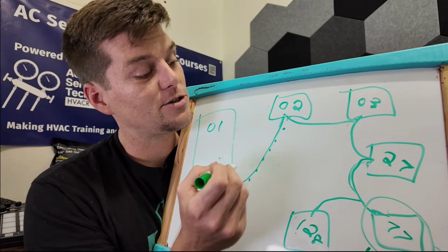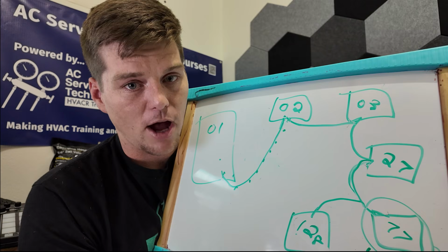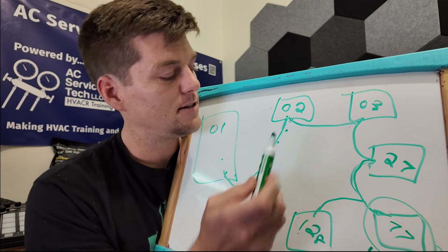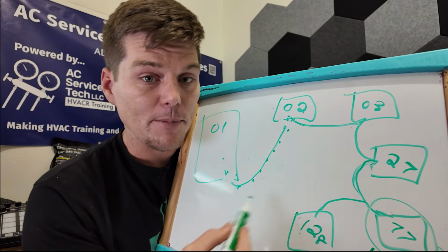Now, if you find that there's a disconnection between the indoor units, if you find that isolating an indoor unit's the problem, don't forget to go back to the basics of disconnecting the wire at both sides and ohming the wire out between the two.